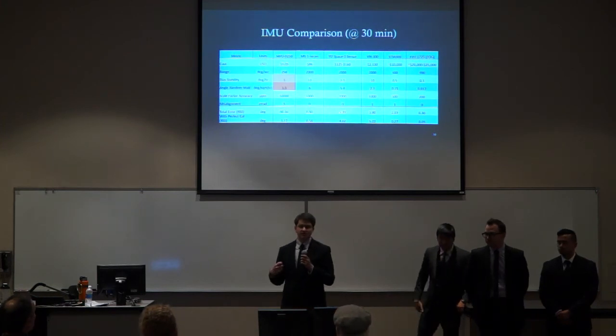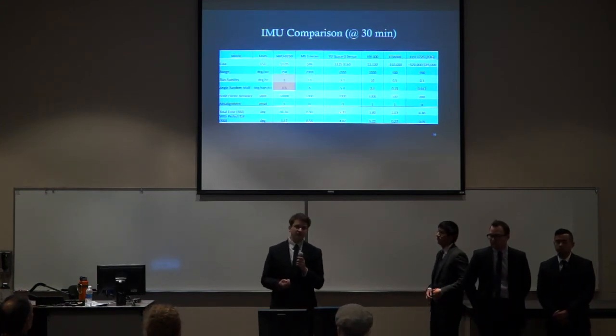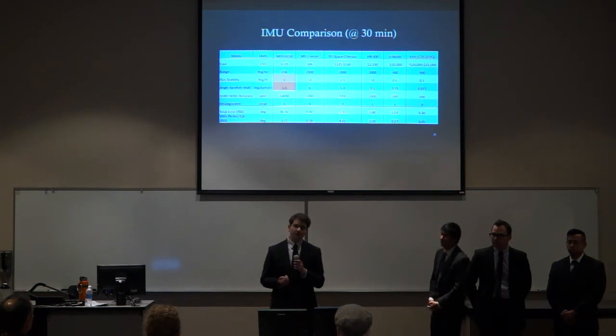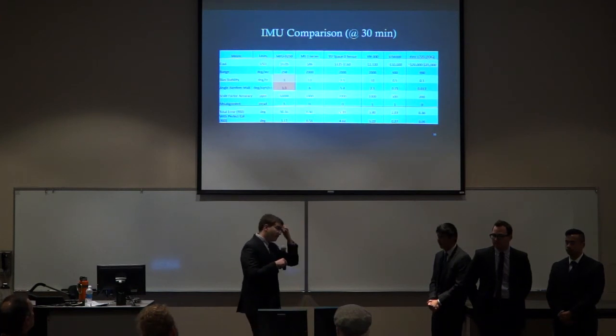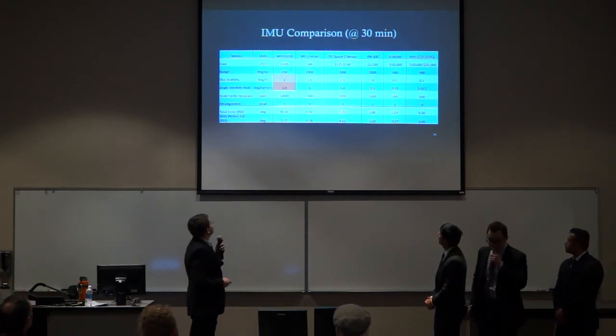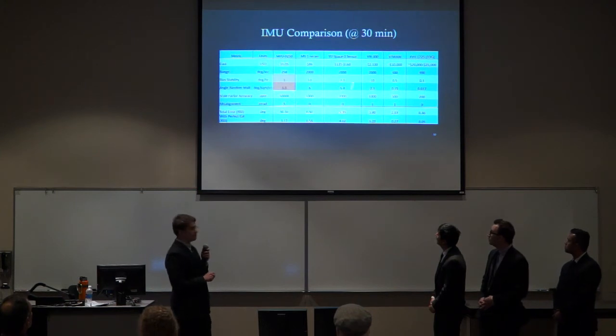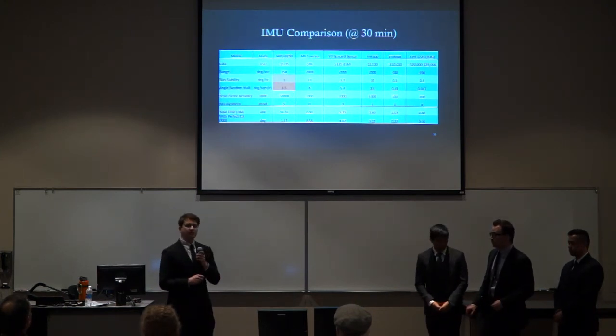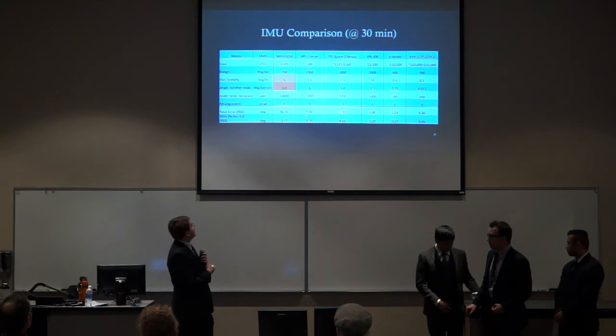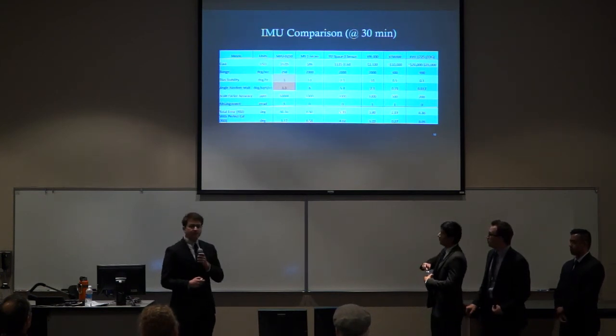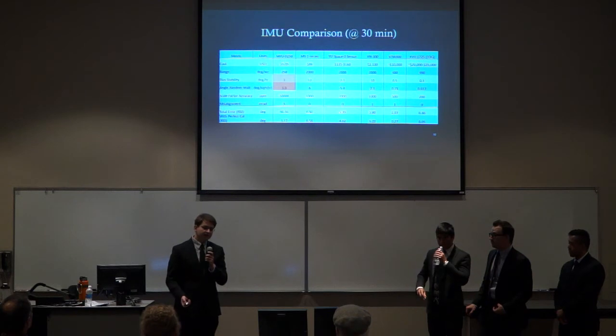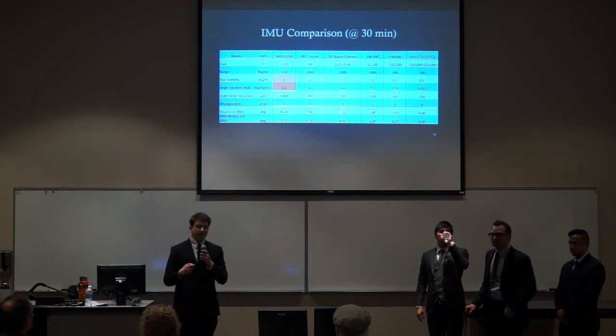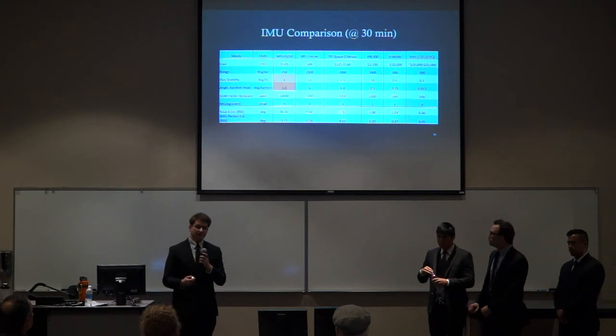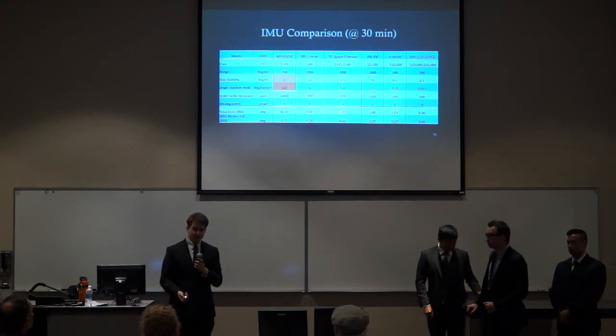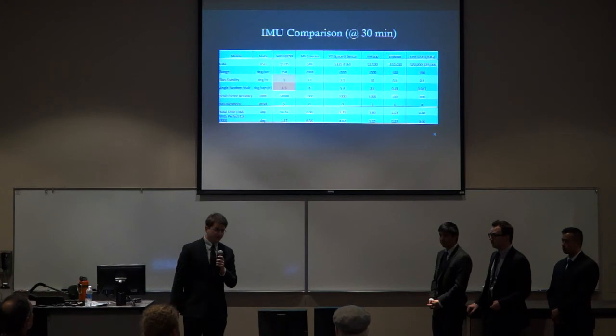So this is our comparison of IMUs. This is just the Z gyroscope, what the orientation reading would be sitting still for 30 minutes. As you can see, the MPU with no calibration, with just these 4 sources of error, the 2 in red we calculated ourselves, is 90 degrees, which is pretty far off. And we have to be within 3 degrees. And this is just the Z gyroscope, not the accelerometers and tracking the position, integrating the position based on our orientation and all of those other sources of error.